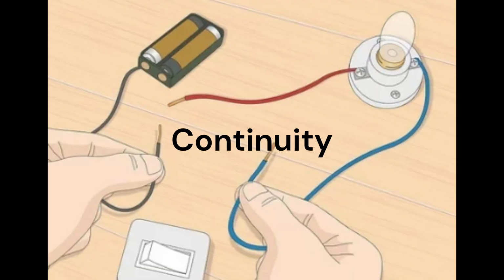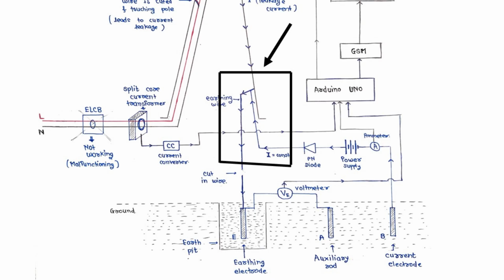For continuity, we also haven't used any sensor here. We have tried to calibrate it with the fall of potential method. So instead of connecting the AC supply directly to the earth electrode, we are connecting it to the earthing wire, so if there is any discontinuity in the earthing wire, that can be immediately reflected through the readings.